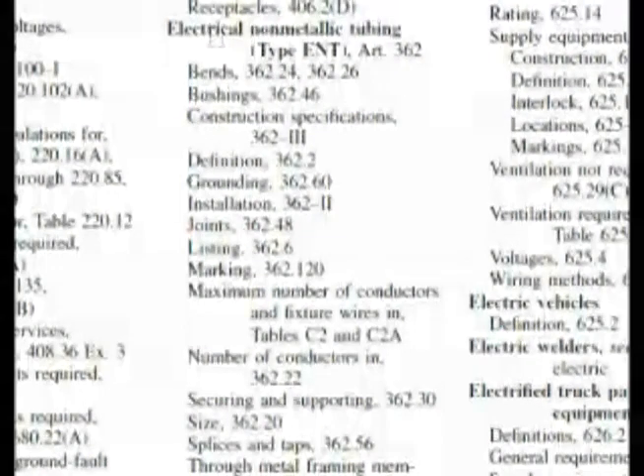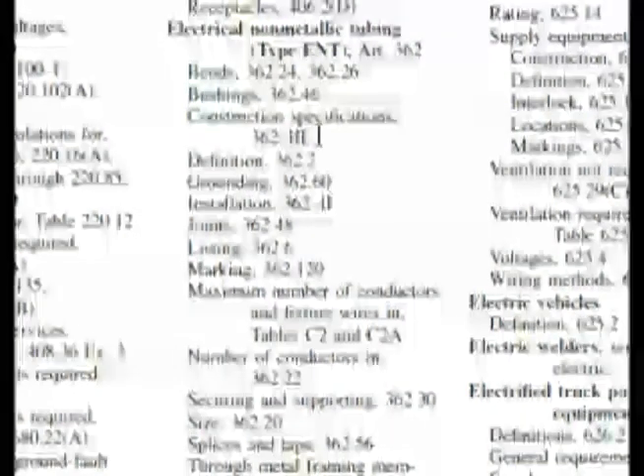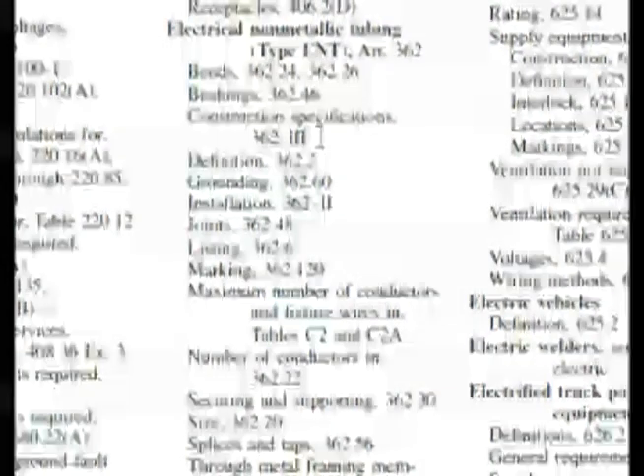Here we are in the index at electrical non-metallic tubing, type ENT — article 362, its own section. Now we drop down and see construction specifications at 362-III. We always need to read down. Installation is at 362-II, and right under it: joints, 362.48. And that is what our question was asking — how to make up joints in ENT. So let's go to 362.48.